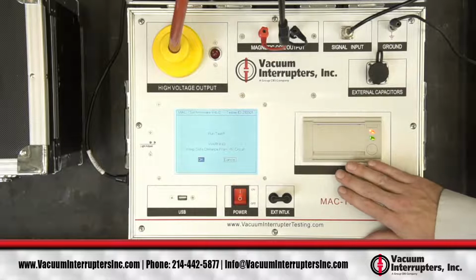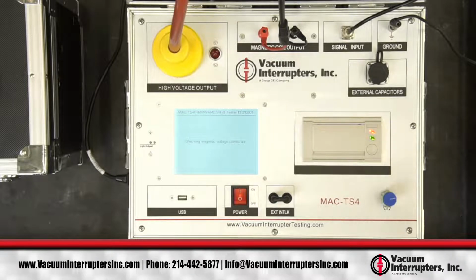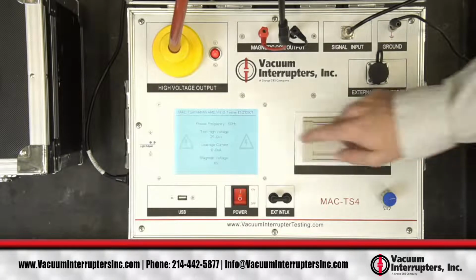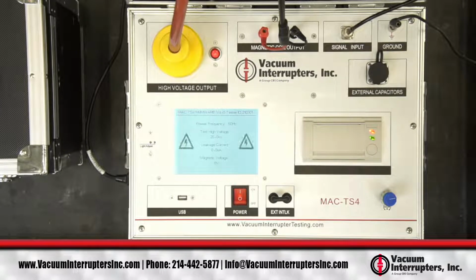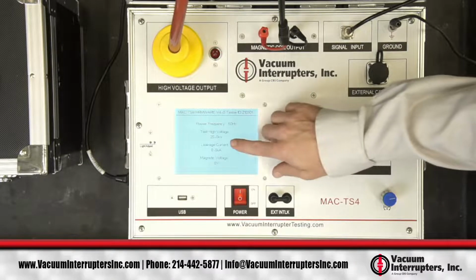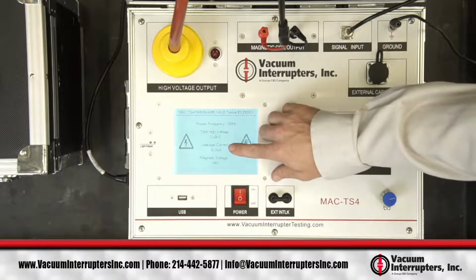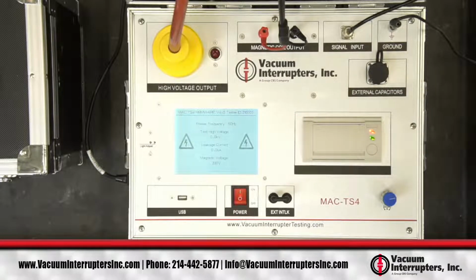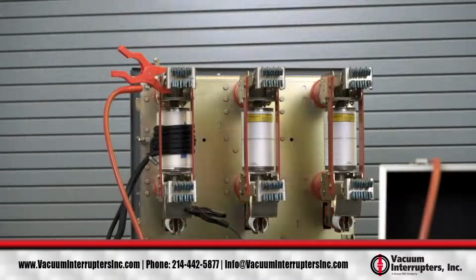So testing. It's making sure you have a coil connected. Applying the high voltage, you get a direct readout of the voltage that's being applied. And you also get a leakage current measurement. So generally this is very low, and in this case it's 0. If you do get a high leakage current measurement, then that could mean there's some problem, too short of a contact gap, or high humidity, or other problems inside the VI. So it is good to keep a lookout at that leakage current.